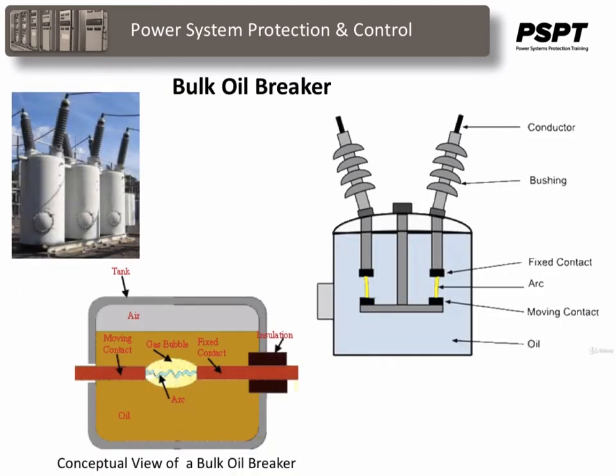One of the oldest types of breakers that are out there and still in service today are the bulk oil breakers. And this is how they work. When the electric current carrying contacts in the oil are separated, an arc is established between the separated contacts. This arc will produce rapidly growing gas bubbles around the arc. As the moving contacts move away from the fixed contact, the length of the arc is increased, and as a result, the resistance of the arc is increased. The increased resistance causes lowering of the temperature and hence reduces the formation of gases around the arc.